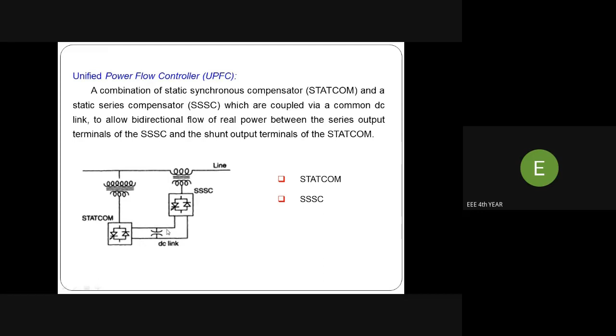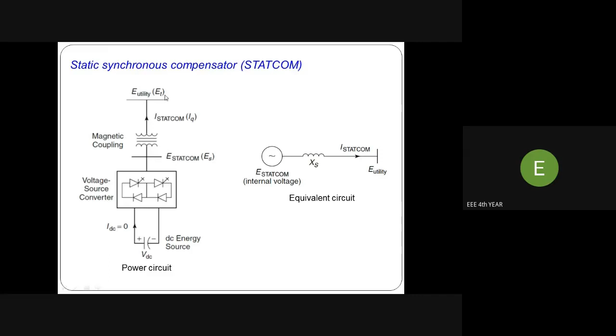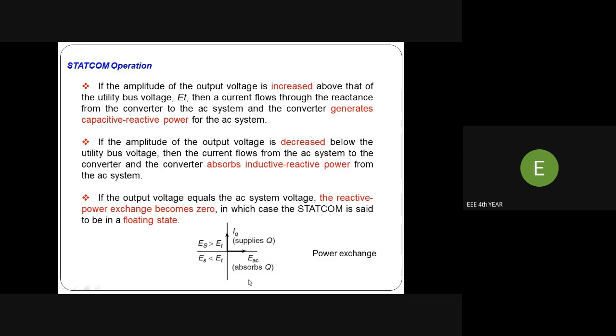In the case of STATCOM, in the circuit arrangement, only shunt connected devices are there. It is a DC energy storage device. We have to inject the current into the transmission line. This is the utility voltage. From the diagram, it either supplies or absorbs reactive power. Supplying reactive power means capacitive reactive power is supplied to the transmission line. At what condition? When the source voltage ES is greater than ET, the utility voltage. If it is reversed, it absorbs inductive reactive power from the transmission line. Based on these conditions, it either supplies or absorbs reactive power.